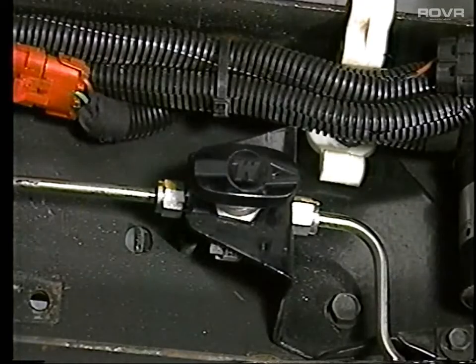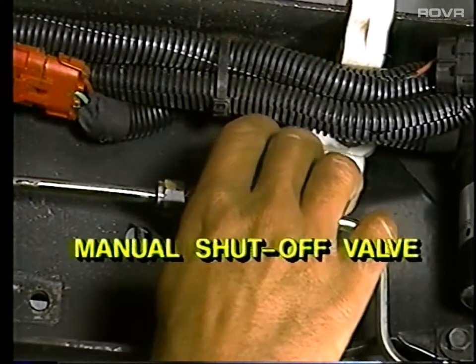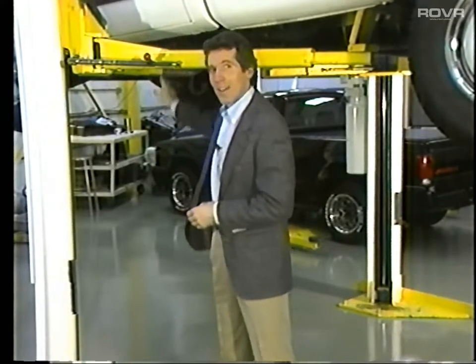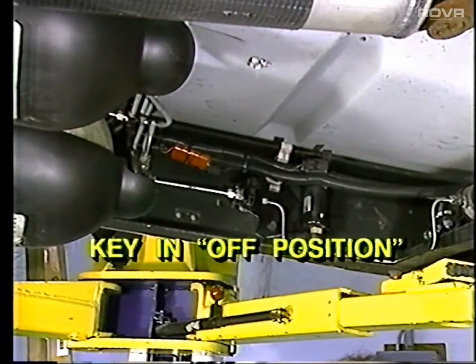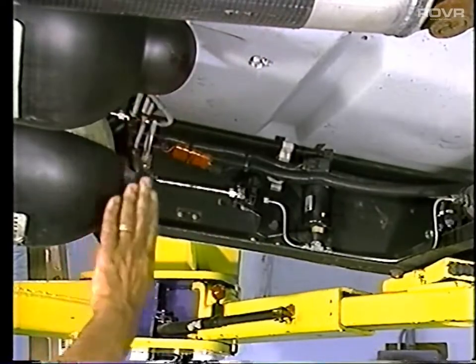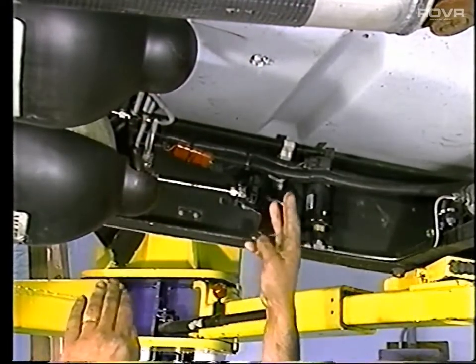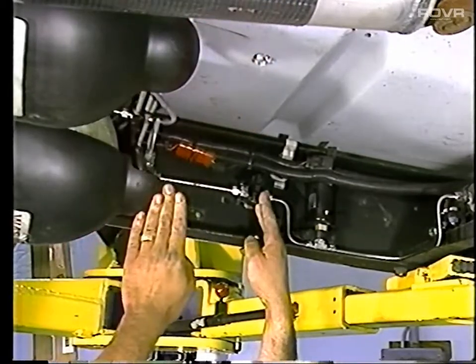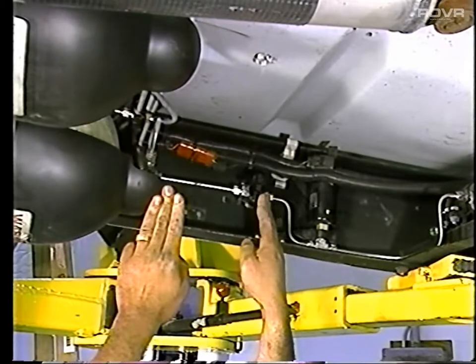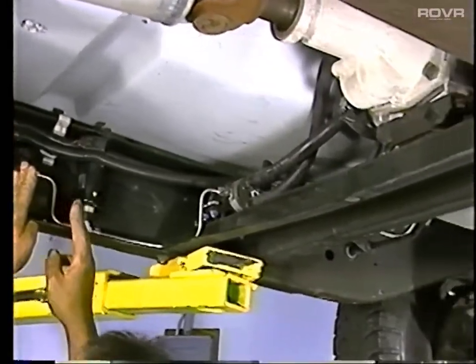First, always stop the flow of gas and vent the line if you're going to loosen or remove any component within the system. You'll stop the flow when you turn the handle of this manual shutoff valve vertically. The valve is located inside the left frame rail, right behind here. Closing the shutoff valve will stop the flow of gas from that point forward, because you've essentially cut the fuel system in half. And when the key is in the off position, the in-tank electric solenoid valves will also be closed, and therefore, the only fuel that can vent into the atmosphere will be that amount held in the line between the storage tank and manual shutoff valve, or from the manual shutoff valve to the injectors. Whichever is the case, it'll be a small amount.